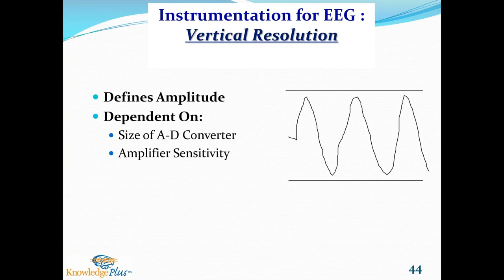Horizontal resolution defines frequency. Vertical resolution defines amplitude. So vertical resolution is dependent on the size of the A to D converter, and you can't change that. You can't go into your equipment, into a settings file, and change the size of your A to D converter. It is what it is, like buying a 4-door car. You can't go back to your dealership and say, hey, I'd like 8 doors on this car. It isn't possible. So the size of the A to D converter is not configurable.